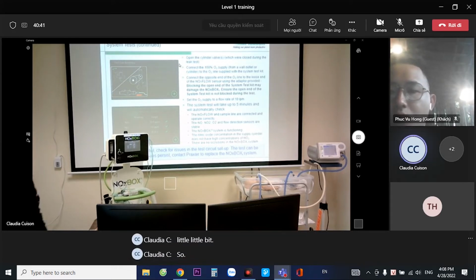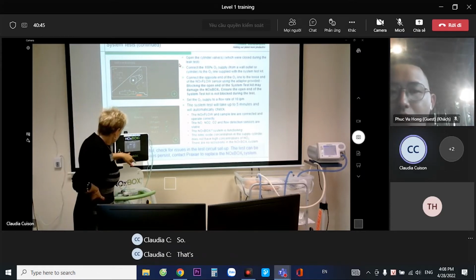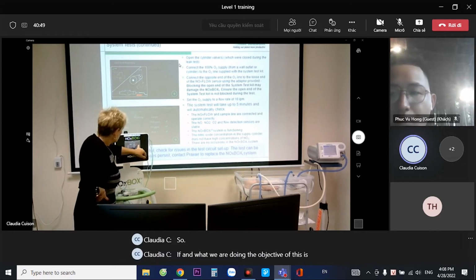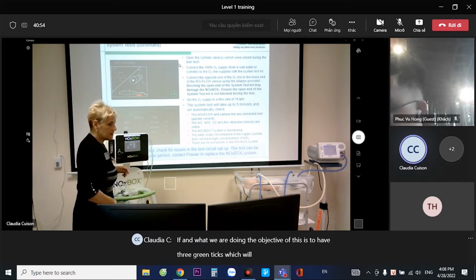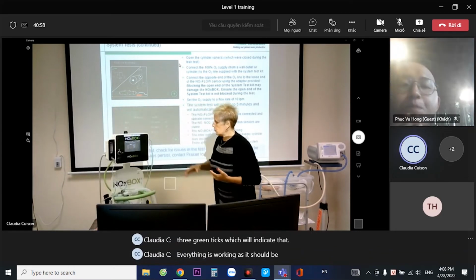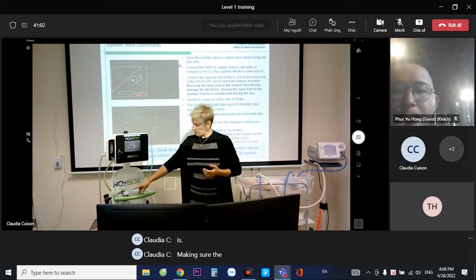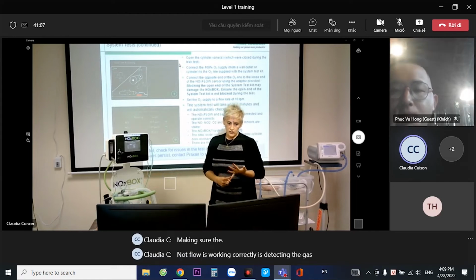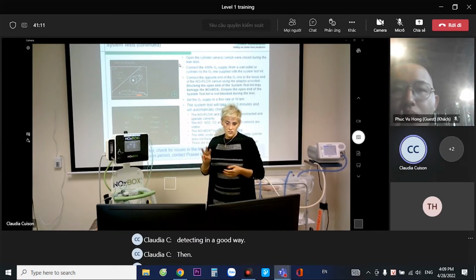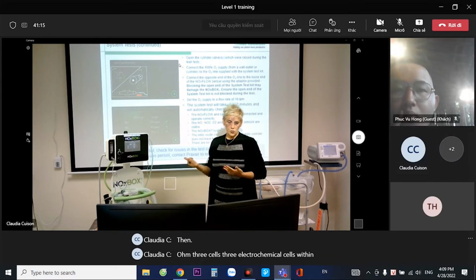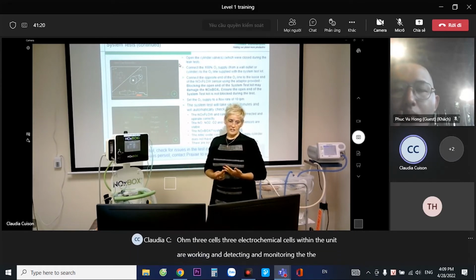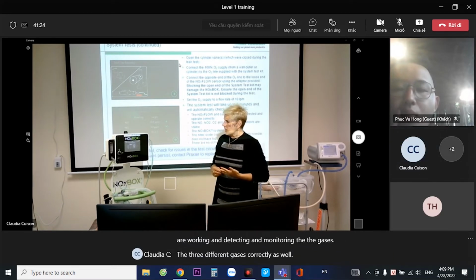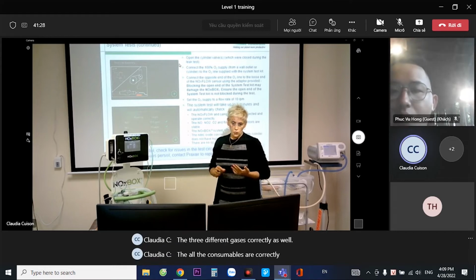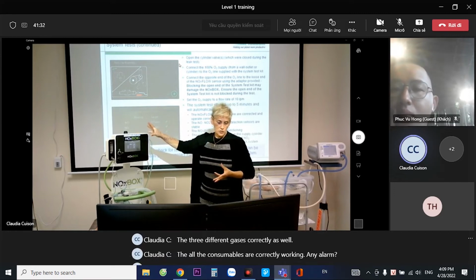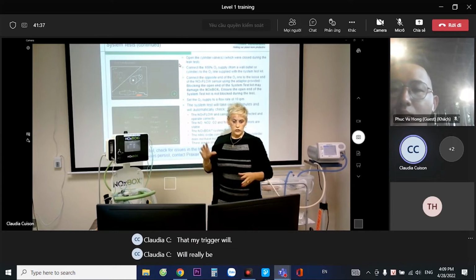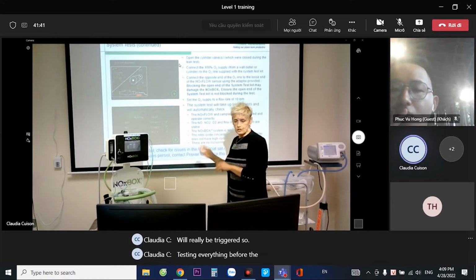So what we are doing, the objective of this is to have 3 green ticks, which will indicate that everything is working as it should be. So what I'm doing here is making sure the NOx flow is working correctly and detecting the gas in a good way. The 3 electrochemical cells within the unit are working, detecting and monitoring the 3 different gases correctly as well. All the consumables are working correctly. Any alarm that might trigger will really be triggered. So, testing everything before the unit is put on a patient.